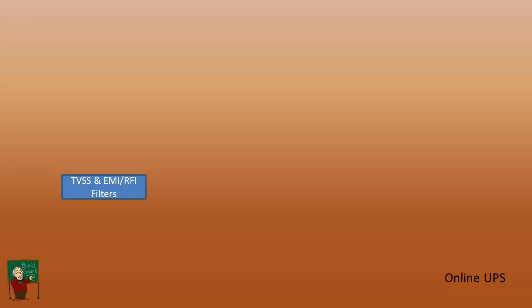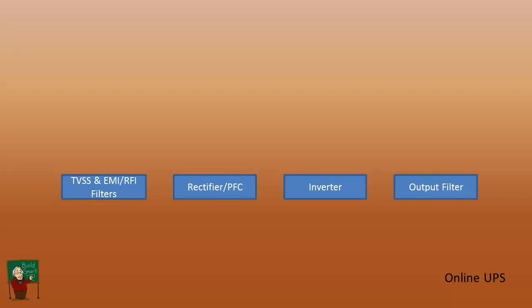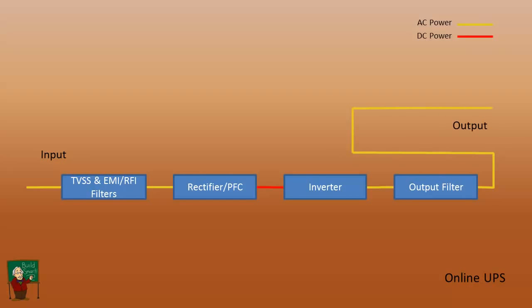We start out with transient suppression and filters on the input. We have a rectifier, power factor correction stage, an inverter, which is what we also had with the standby UPS, and then finally an output filter. We basically connect these together. After the input filter is the rectifier. It converts to DC. That DC goes into an inverter, which in turn goes to the output filter, and it provides the output of the unit. So essentially, this works full-time running these stages.